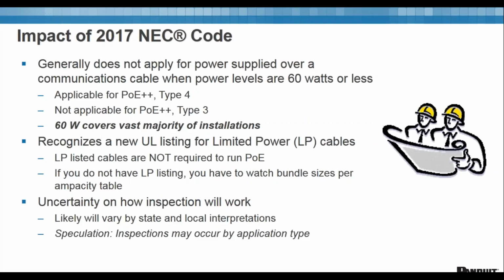you put your cable in before you really are putting your equipment in. So if someone's coming in to inspect it and saying, well, this is going to be a Type 4 and this is a Type 3, nobody really knows, right? How do you know what goes where? Speculation, and this is only speculation, is that inspections may occur by application type, meaning where the cables are going might impact what LP rating, or if they need an LP rating or not.